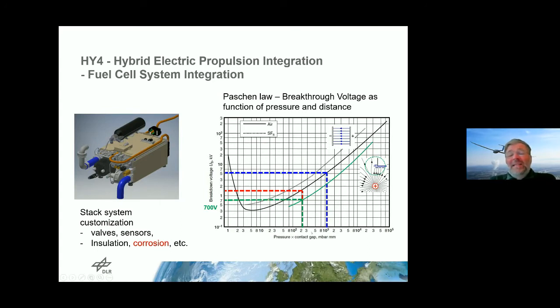And then we see that if we stay very low in geometrical distance between the conductors, we can even have a breakthrough at 700 volts, maybe at 1,500 volts, depending on the geometry. If it's parallel, it's higher. If it's with edges, with sharp edges, it's lower.